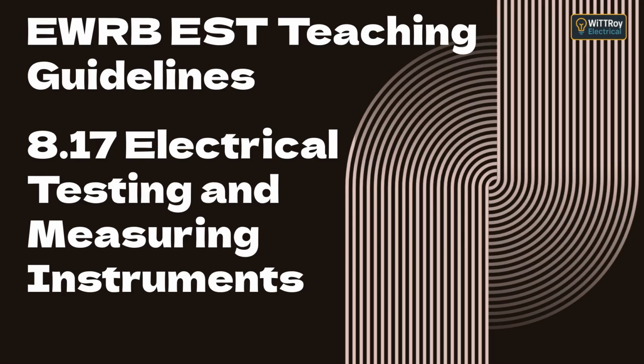Topic E. Safe use and maintenance of test instruments. Now let's move to Topic E. Safe use and maintenance. Before using any test instrument, inspect the meter and leads for cracks, cuts, or exposed conductors. Check the probe tips are tight and clean. Verify the meter's function by testing it on a known live source before and after use, the same prove test prove rule you learned earlier.